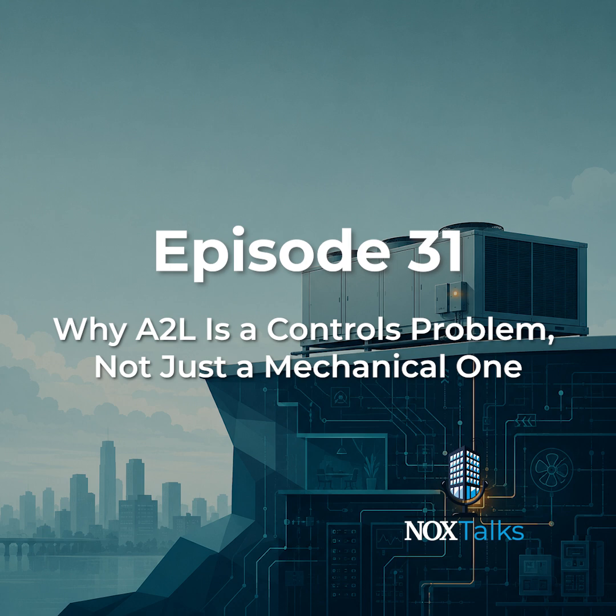So when you replace a unit, you're often stepping into a lower GWP refrigerant with what's called an A2L safety classification. You'll hear two names a lot: R-32 and R-454B. Quick decoder. That label's an ASHRAE safety class. The A means lower toxicity, the 2L means lower flammability, low burning velocity. So A2L isn't a chemical family, it's a safety rating. Mildly flammable. Not in the same risk category as propane, not something to sensationalize, but flammable enough that the codes treat it differently. And that's where it stops being a simple swap of the gas.